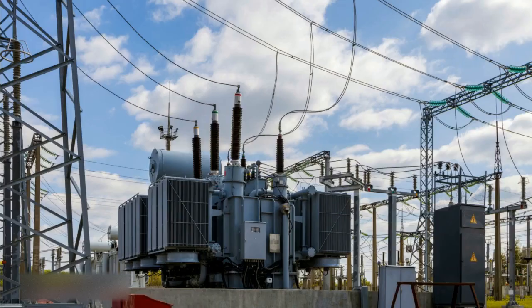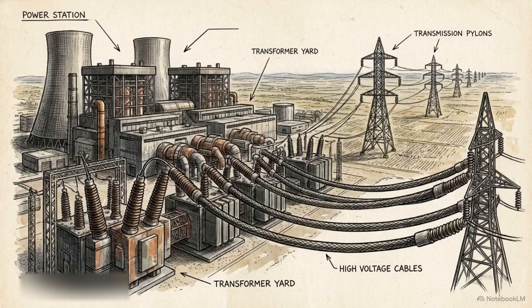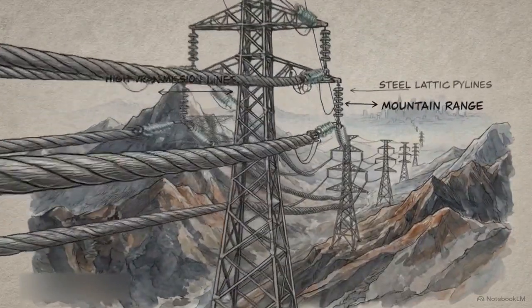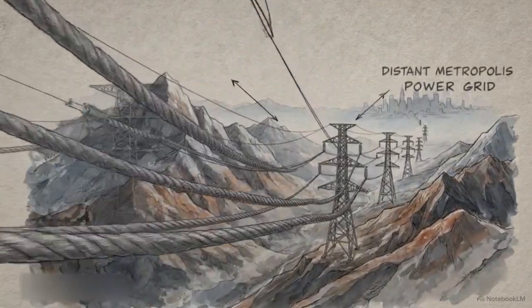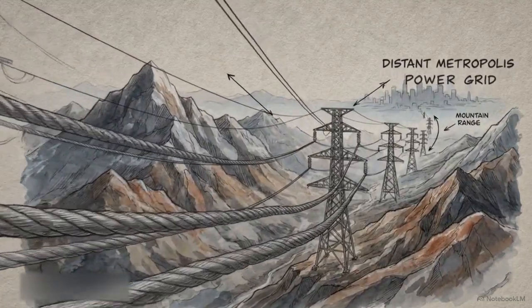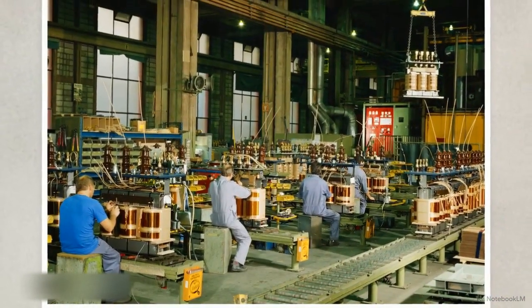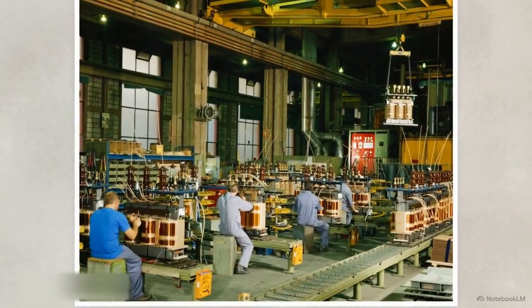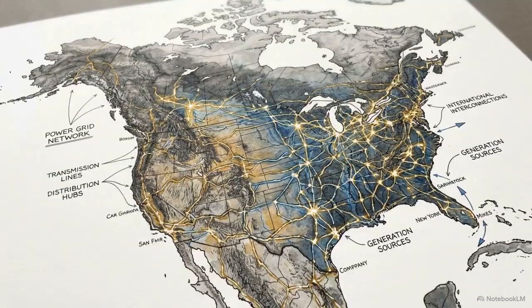On the grid, these machines operate within high-voltage substations, often for 50 years or more. They take the output from generating stations and step it up to 400,000 volts for transmission. The power travels across the country with minimal heat loss before being stepped back down for safe use in homes and businesses. This process requires the industrial assembly of thousands of optimized cores and windings to sustain the national infrastructure. By balancing the ideal mathematics of induction against the thermodynamic realities of the hardware, the transformer enables the stable, continental-scale distribution of electrical power.